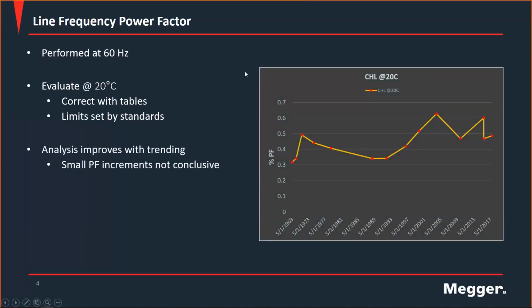So what can you do after you correct if you are looking for a little bit more information on the changes in the asset? Well, you can trend those points in data over time. However, even if you have the data, and I would challenge a lot of people to see if they even have this historical data for reference, if you do happen to have it, the small changes that you may see in power factor are not conclusive to any drastic changes within the transformer at line frequency. There was also a part in Robert's presentation that alluded to that as well, that line frequency power factor is not sensitive to early and advanced changes in moisture and liquid conductivity.